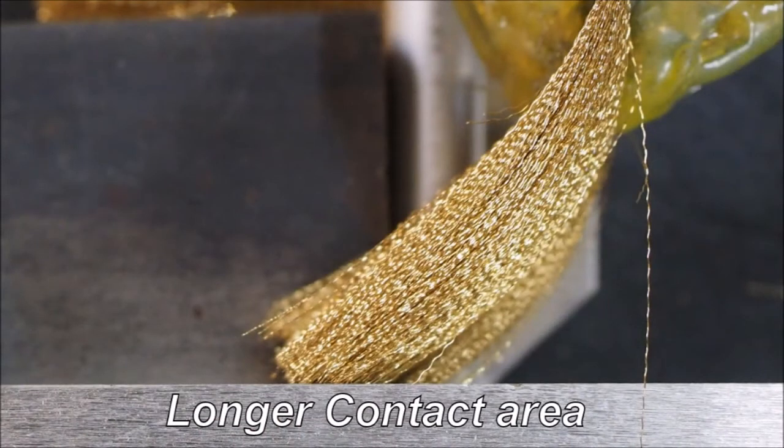So you want to be very careful as to how fast you move, how much gap you've got by pulling the coil up too tight. The brush, as you can see, the contact area is much, much larger. It's there for longer. So you have more chance of finding a flaw with a brush than you do with a coil.